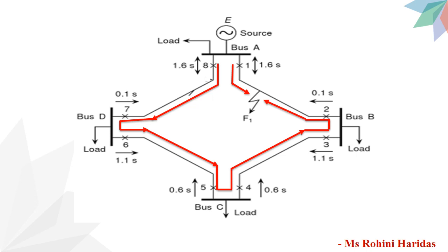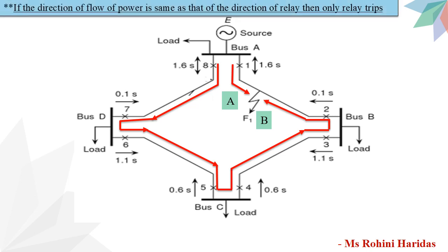Let us assume a short circuit occurs at point F1 as shown in the figure. In order to ensure selectivity, it is desired that only circuit breakers at relay 1 and relay 2 should open to clear the fault, while other sections of the ring remain intact to maintain continuity of supply. Power will be fed to the fault via two routes: route A — from E to A to F1, and route B — from E to D to C to B to F1. We have incorporated directional as well as non-directional relays along with the time grading principle.